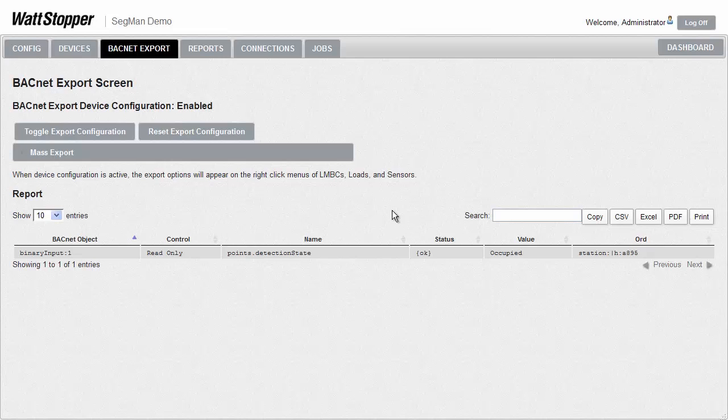When the integrator asks for info from the segment manager, it doesn't have to send a command down the network wire to the individual device. We know to keep that information right at the ready here in the export table. That also helps us avoid situations where an integrator might be pulling for data too quickly. Without the export table, we could be overwhelmed trying to send and receive data for all the requests that an integrator is making. The integrator benefits from this as well because there's very little latency from when they ask for information to when they get a response. The export table is a feature that's a huge benefit to everybody dealing with integration.